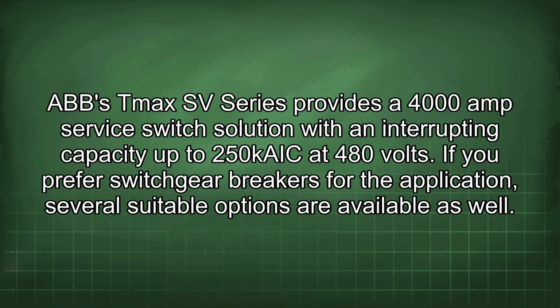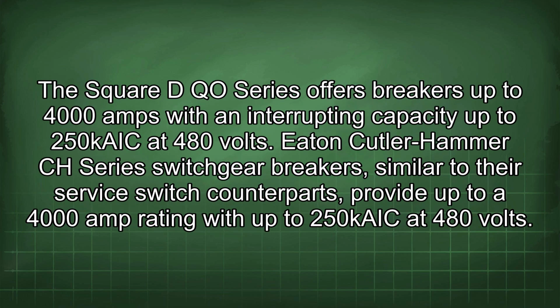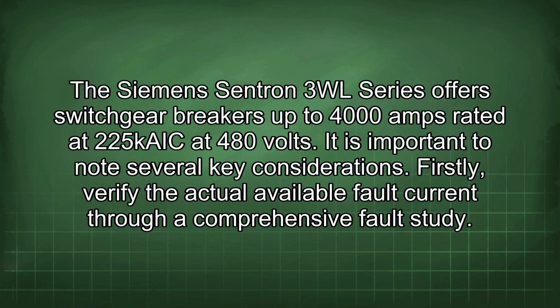ABB's Tmax SV series provides a 4000 amp service switch solution with an interrupting capacity up to 250kAIC at 480 volts. If you prefer switchgear breakers for the application, several suitable options are available as well. The Square D QO Series offers breakers up to 4000 amps with an interrupting capacity up to 250kAIC at 480 volts. Eaton Cutler-Hammer CH Series switchgear breakers, similar to the service switch counterparts, provide up to a 4000 amp rating with up to 250kAIC at 480 volts. The Siemens Sentron 3WL Series offers switchgear breakers up to 4000 amps rated at 225kAIC at 480 volts.